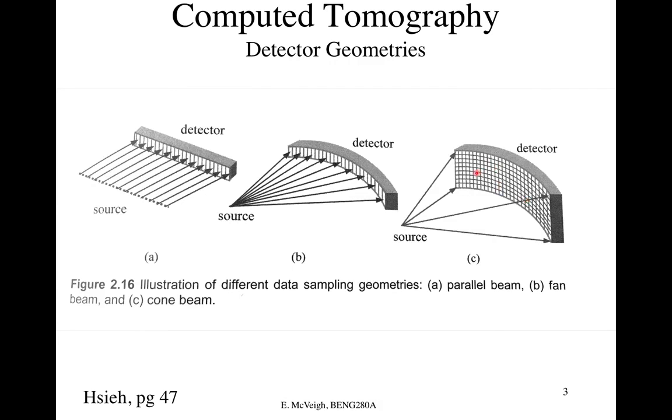The way these things are designed right now, in 99% of CT scanners that are sitting in hospitals, the separation between these pixel elements, or sometimes they're called detector elements or dexels as opposed to pixels, is usually about 1 millimeter, plus or minus 10%. Can we bring down the sampling rate? The maximum sampling rate is fixed for a particular device. So the question is, can we bring down the sampling rate? Yeah, okay.